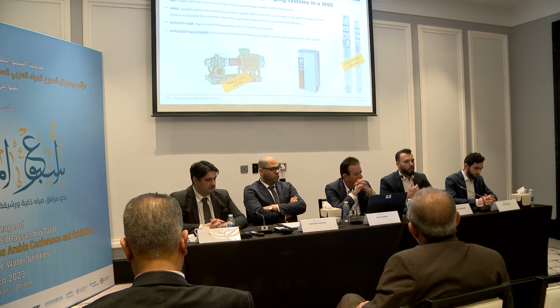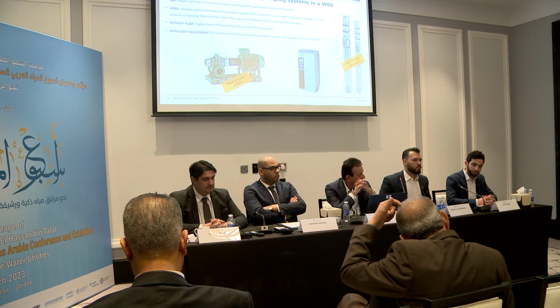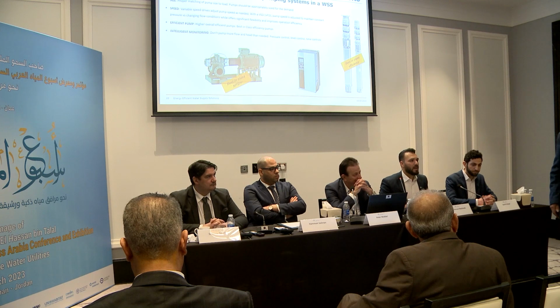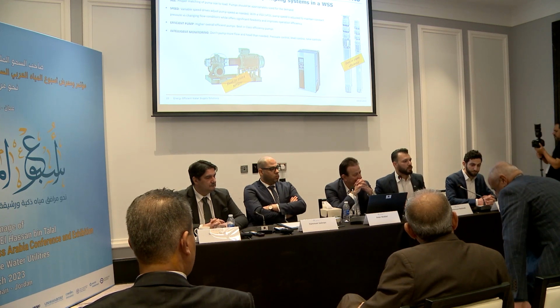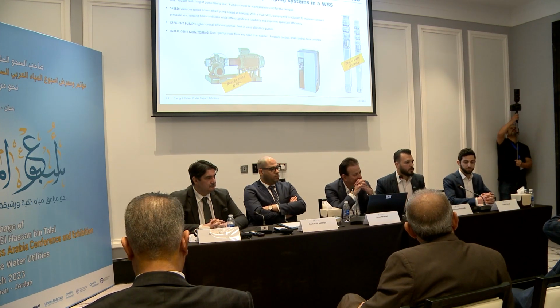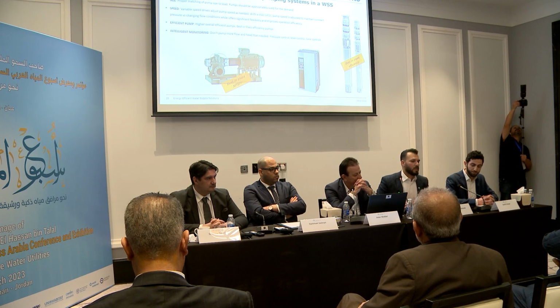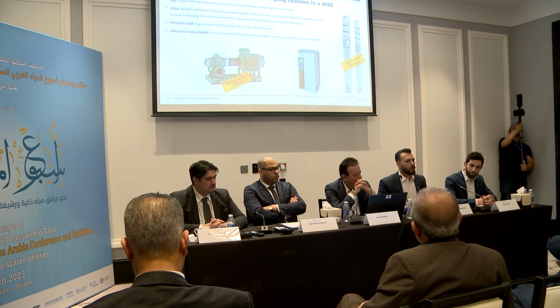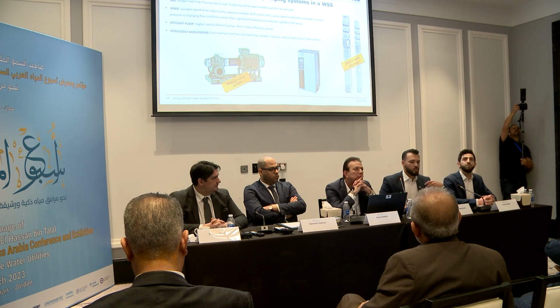So, how to improve it? First, from the design stage, proper matching or proper sizing of the pumps to match your demand or future demand as well. Second, you can use variable speed drives to control your pumps and work at a constant pressure with variable flow. There are also some intelligent monitoring and control systems.